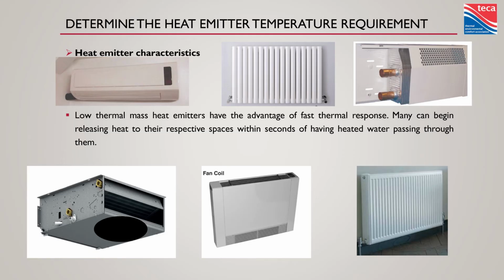So ductless or ducted fan coils exist. They come in lots of different flavors: slim duct, central duct, whatever format you prefer. Pipe it to drain, get rid of that latent heat. You'll have a much happier system. You can use some radiant floor in conjunction with forced air chilled water cooling to try and cut down on some of that sensible load and do it with the efficiency of hydronics, but you're going to need some air movement anyway.